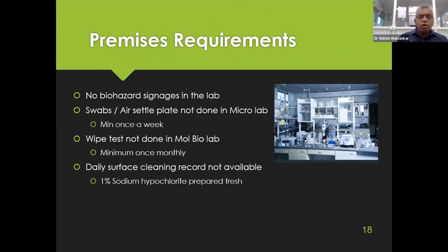Daily surface cleaning record not available is again a very common NC. 1% sodium hypochlorite prepared fresh is what is required. There have to be records of training of the housekeeping personnel for preparing this 1% sodium hypochlorite. Usually, commercially, what is available is around 4 to 5%, and it needs to be adequately diluted, 1 in 4 or 1 in 3, in order to achieve a 1% sodium hypochlorite solution. It needs to be prepared every day in the morning and then dispensed at all the laboratory benches and then discarded at the end of the day.